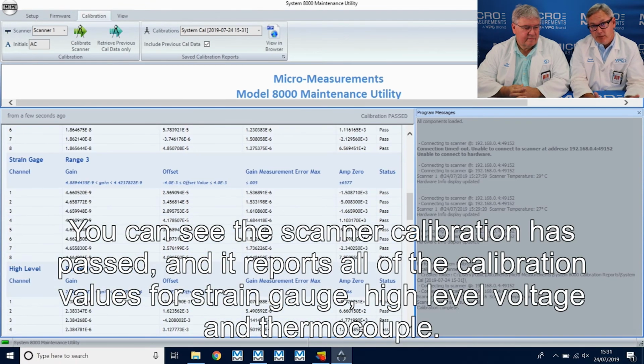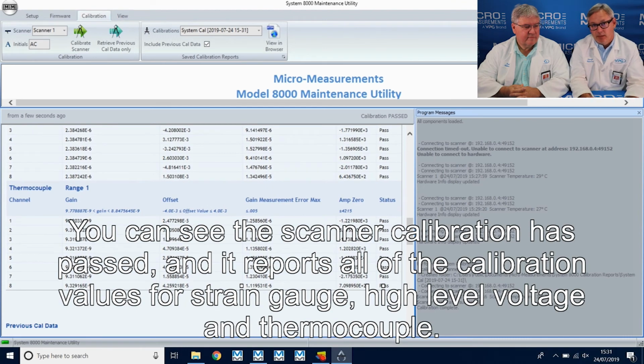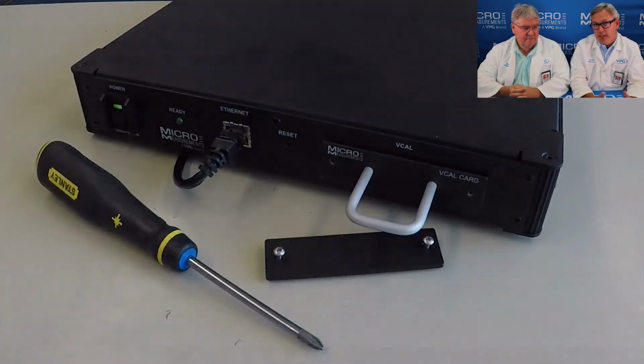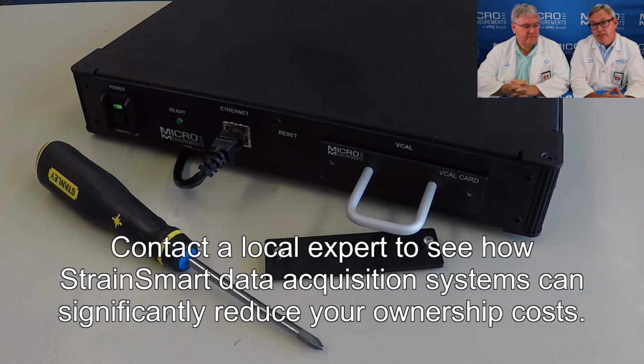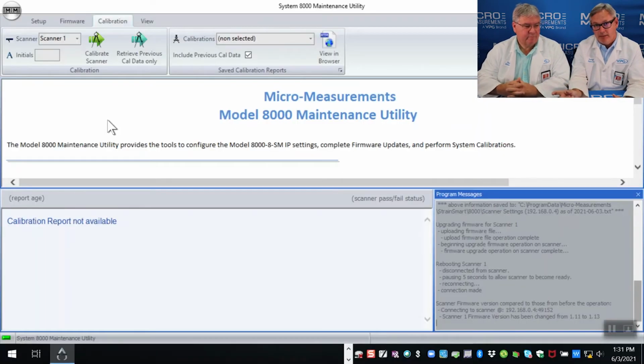If it's within spec, it'll report back that it's met the calibration. If it's not within spec, then you're looking at potentially sending that scanner out for repair. But the cool thing about these VCal cards is that that's the only thing that you have to get calibrated periodically by the manufacturer, Micromeasurements, is that small VCal card. And you can ship that out to us and continue to use your scanner while we're calibrating your VCal card and sending it back.